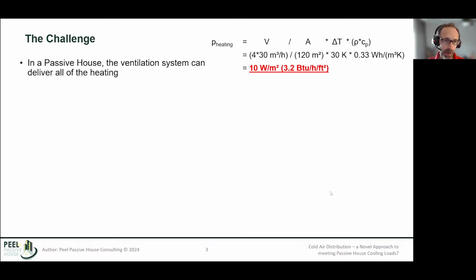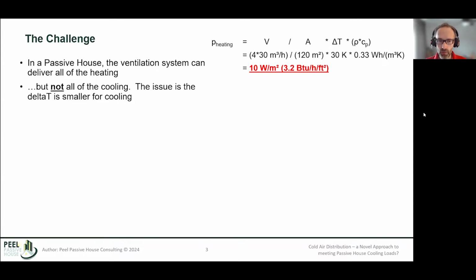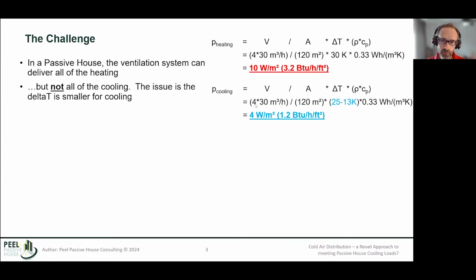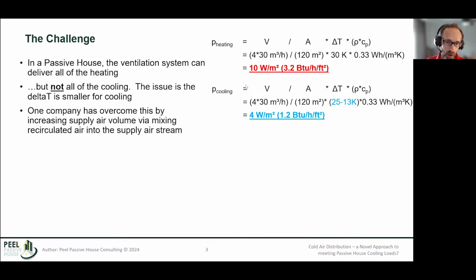Generally not done, right? And part of the reason is that we can't do that with cooling. If we apply the same formula to the cooling case, essentially we have a much lower capacity of the ventilation air to deliver cooling. A key reason is that the delta T from room temperature to our supply delivery temperature is just smaller in cooling mode than in heating mode, right? And so we get a smaller capacity and can't meet our loads.